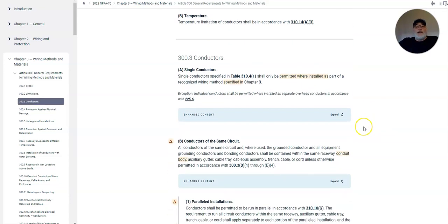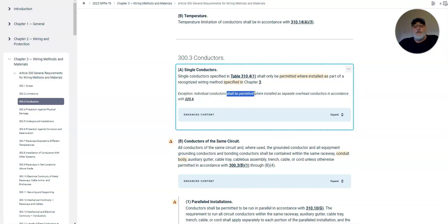Okay, so let's look at the conductors themselves. 300.3 talks about conductors. Single conductors specified in 310.4.1 shall only be permitted where installed as part of a recognized wiring method system or wiring method specified in Chapter 3. Now, there's an exception. Okay, I want you to always pay attention. These exceptions may trigger you to have to go look somewhere else in the code book. Individual conductors shall be permitted. Remember, we talked about this the other day. Shall, not, can, if. Those are trigger keywords. Shall be permitted where installed as a separate overhead conductor in accordance with 225.6. Okay.